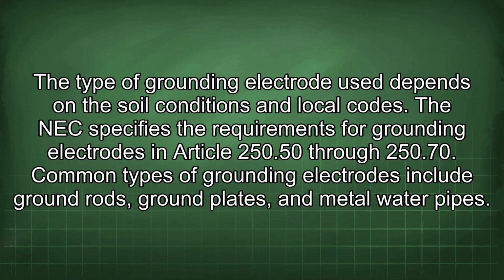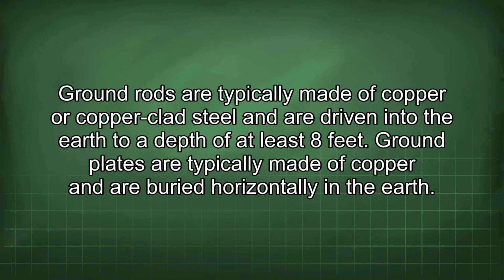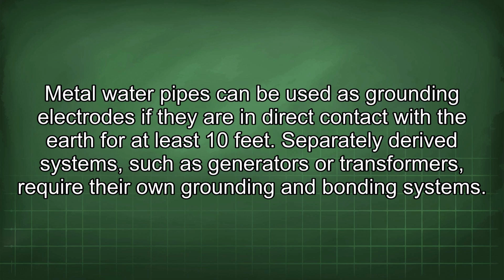The NEC specifies the requirements for grounding electrodes in Article 250.50 through 250.70. Common types of grounding electrodes include ground rods, ground plates, and metal water pipes. Ground rods are typically made of copper or copper-clad steel and are driven into the earth to a depth of at least 8 feet. Ground plates are typically made of copper and are buried horizontally in the earth. Metal water pipes can be used as grounding electrodes if they are in direct contact with the earth for at least 10 feet. Separately derived systems, such as generators or transformers, require their own grounding and bonding systems.